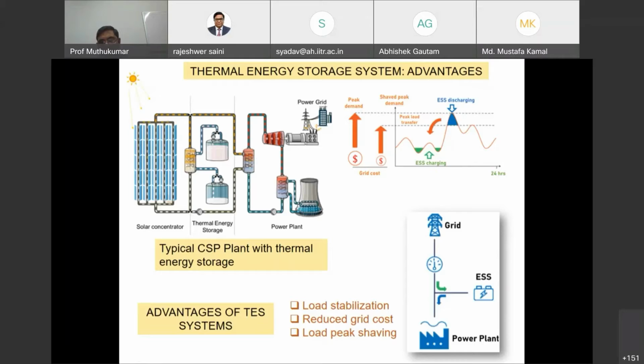So this thermal energy storage system serves in several ways and provides a lot of benefit. It brings down the levelized cost, particularly in solar thermal power plants. Without storage, the cost of electricity generation from solar thermal is approximately 10 to 12 rupees, but with storage it comes down to about 4 to 5 rupees, which is comparable to coal-fired thermal power plants at the actual rate. It also increases the reliability of the system and improves the capacity without needing major additional components. There are several ways thermal energy storage can help solar thermal power plants.